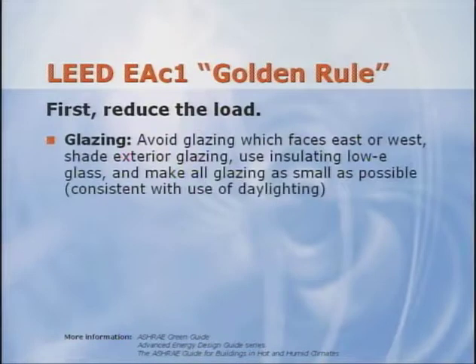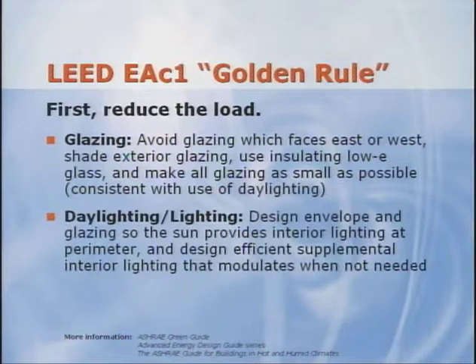Minimize glazing, which faces east or west. Shade exterior glazing. Use insulating low E glass, and make all glazing as small as possible. Design the building envelope and glazing so the sun provides interior lighting at the perimeter of the building, a concept called daylighting. Then design efficient supplemental interior lighting that modulates when it's not needed.